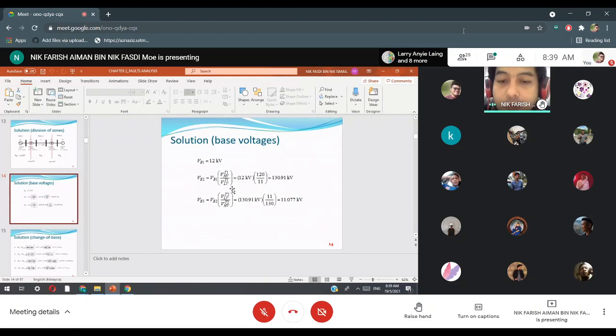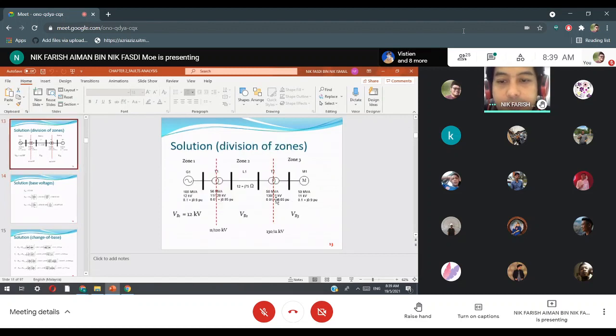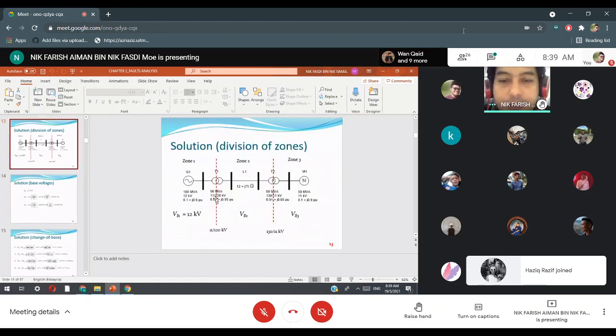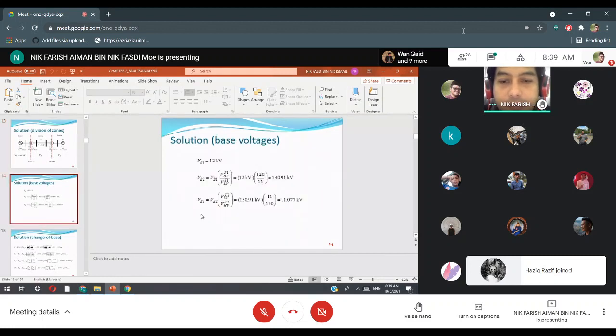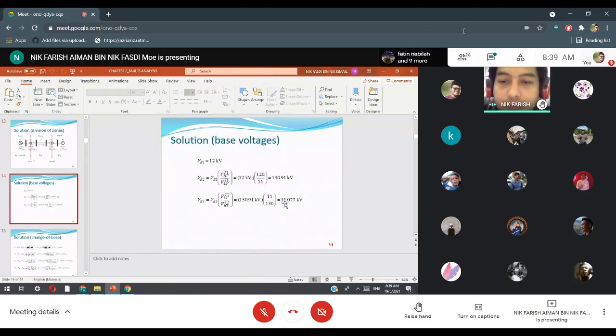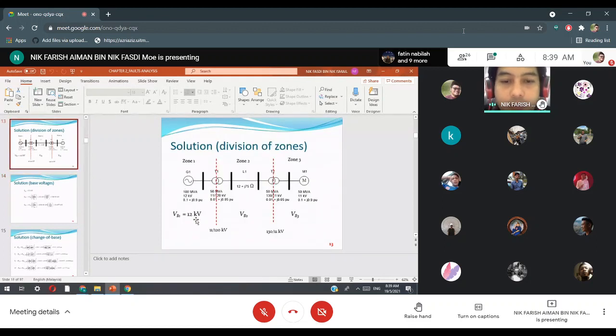The rating for transformer 2 low voltage side is 11 kV. This is 11 kV divided by 130. So there you can obtain the value of VB3, which is 11.077 kV. Now we have all the values for VB1, VB2 and VB3.